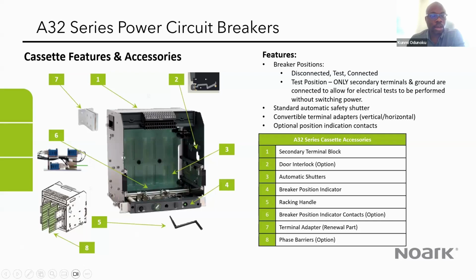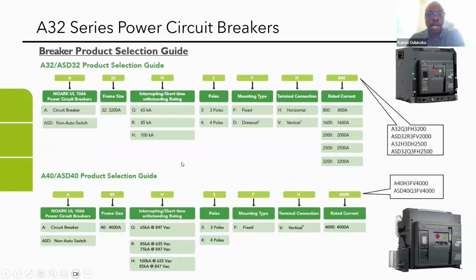the accessories that come with it. The rear terminal connectors are applicable to both the fixed and the draw out. Anyway, we have the safety shutter that protects the personnel once the breaker is withdrawn, so that the live parts of the breaker are not exposed.